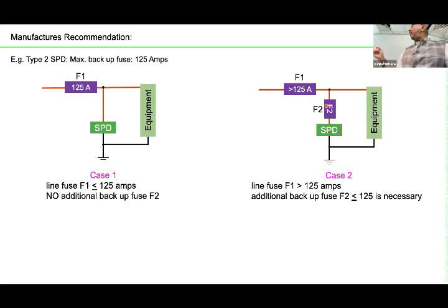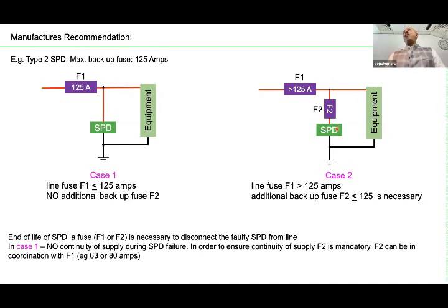So as a result, generally what people think is, okay, if the fuse is, let's say, 100 amps or up to 125 amps, this additional fuse is not required. As a result, they go for the connection type F1, this connection type 1 on the left side. If the current rating of the circuit is more than 125 amps, they put an F2, an additional backup fuse. Actually, this is one of the very complicated subjects to decide.